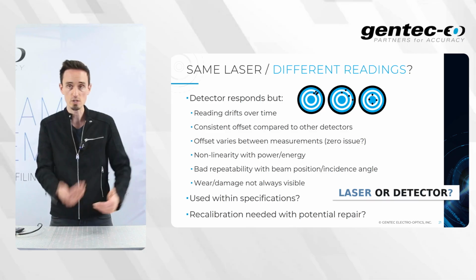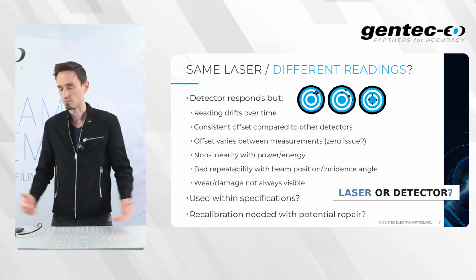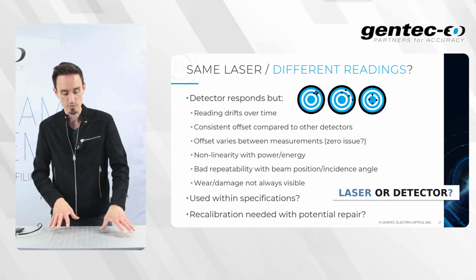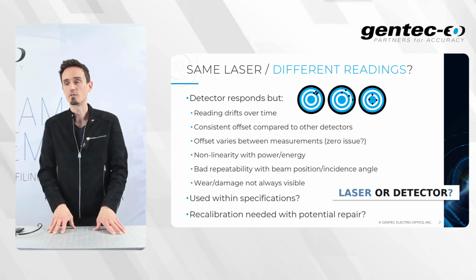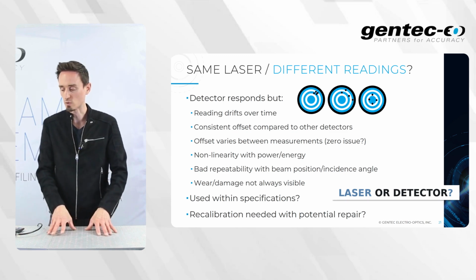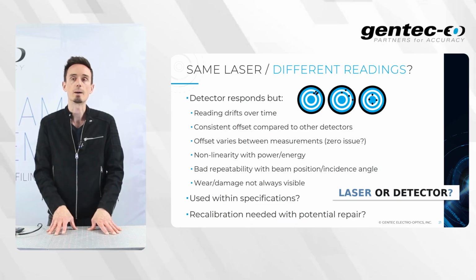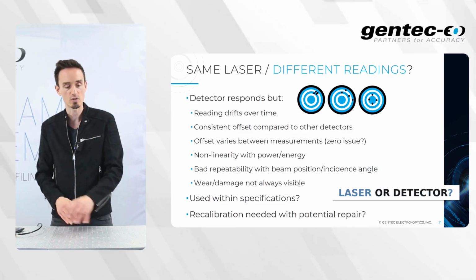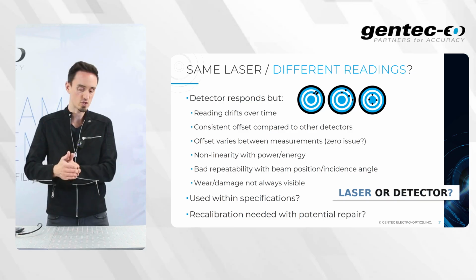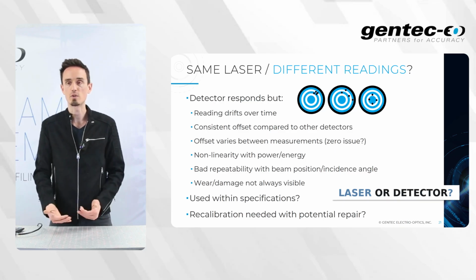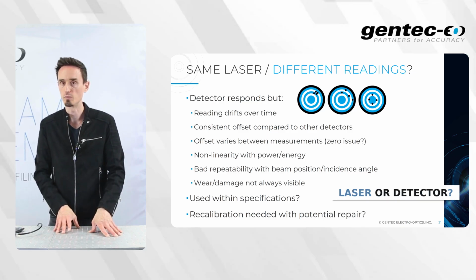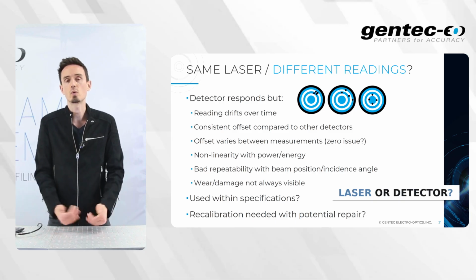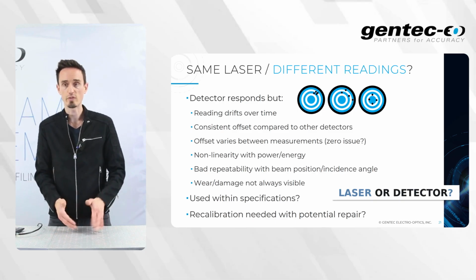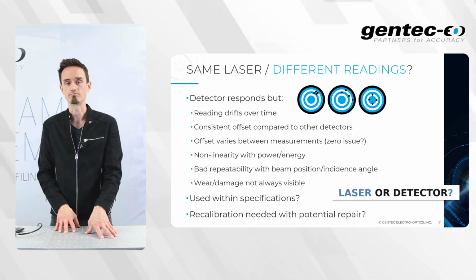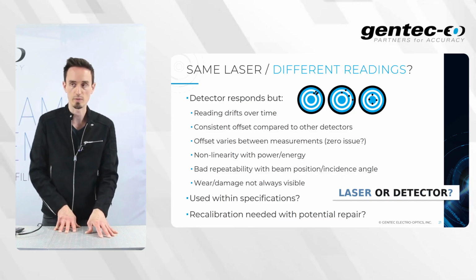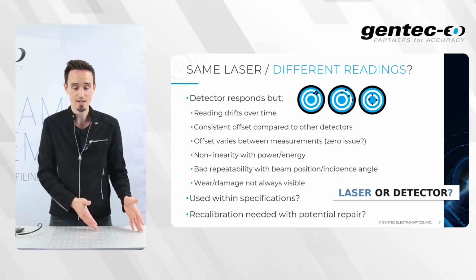Is that a zeroing issue? People could run various different types of zeroing features, but there are some tools on software that are usually very easy to use. You could see some nonlinearity with power or energy, or bad repeatability, depending on the beam position or incidence angle, and some wear or damages internally that's potentially not always visible. So in those cases, first question is, is the detector used within specs, right? And then, do I need to consider recalibration with a potential repair? Question is, is it coming from the laser again, or the detector?